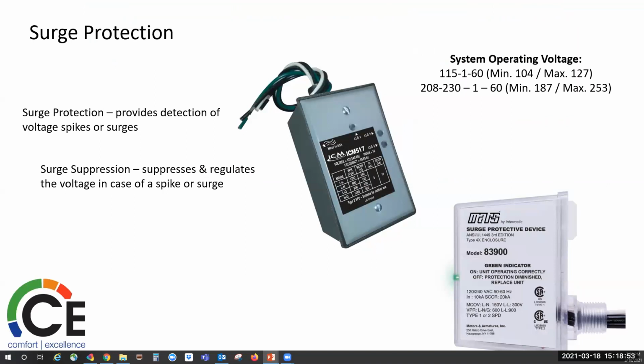Surge protection, if you got a voltage issue, problem, or just want to protect the system, if you have a lot of brownouts, fluctuation in voltages, you might consider installing a surge protector. If you have unexplained compressor and board failures, it might be the fact that your incoming power is doing something and you're not there to catch it at that time. And this is a good idea to install these and help protect the system.